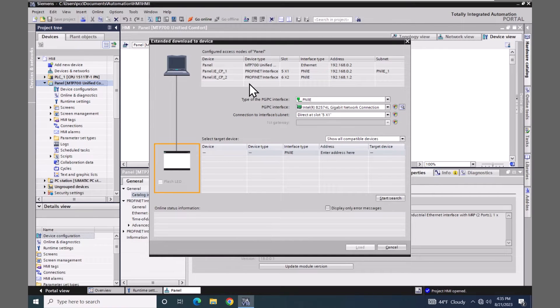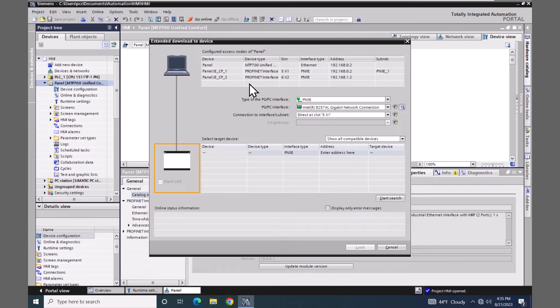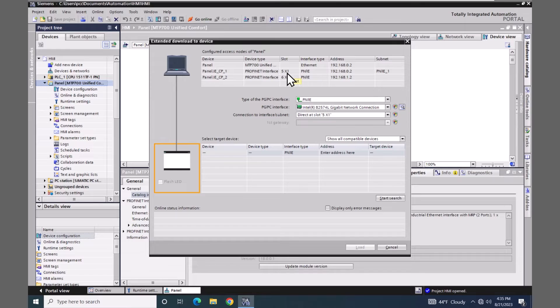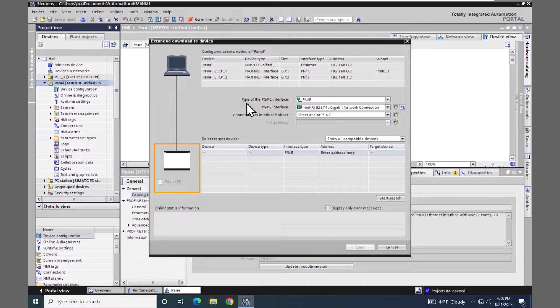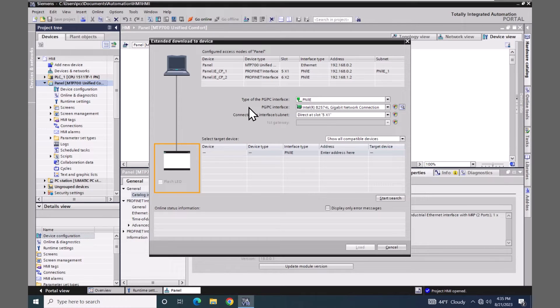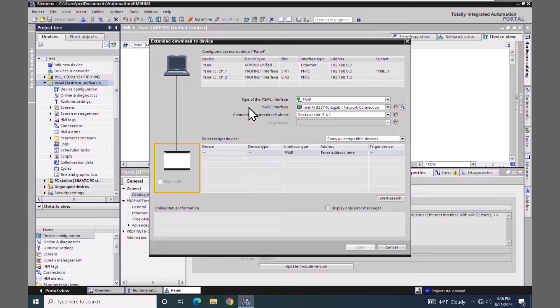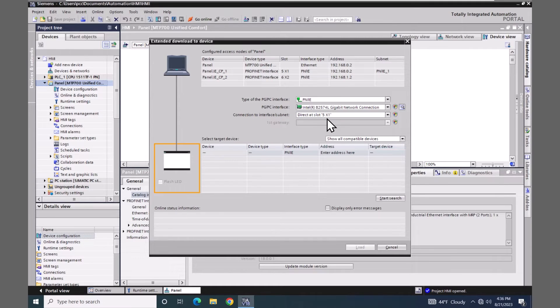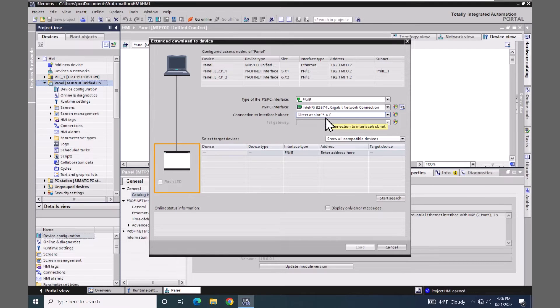This top area here has the different slots or ports that are configured in the IP addresses on the unified comfort panel. We are going to be downloading to the slot 5x1, so we'll have to pick that down here in the configuration. The type of PG interface for the transfer can either be PN/IE or Ethernet. Typically you're going to use PN/IE unless you're going to be updating the operating system, then you would have to pick an ethernet connection. The PG/PC interface is the network adapter on your computer that has access to the unified comfort panel that you want to download to. The connection to interface subnet is the actual IP address that you're going to try to transfer to, so the 5x1 is going to be the 192.168.0.2 in this case.